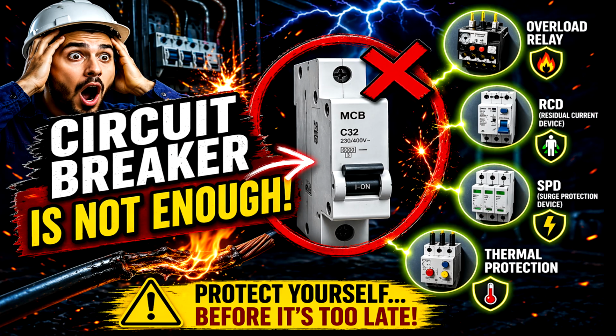Day after day, the insulation weakens until suddenly... Second danger, poor connections. A loose screw, a weak terminal, a bad contact point. All of this creates high resistance, and resistance equals heat. But the breaker? It doesn't even notice it. Third danger, oversized circuit breaker. One of the most common mistakes. People often say, let's install a bigger one so it doesn't trip. And just like that, you've basically disabled the protection. The wire can burn, and the breaker won't even react.